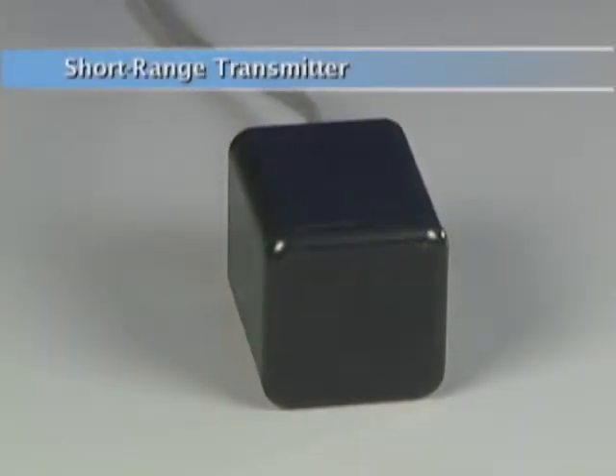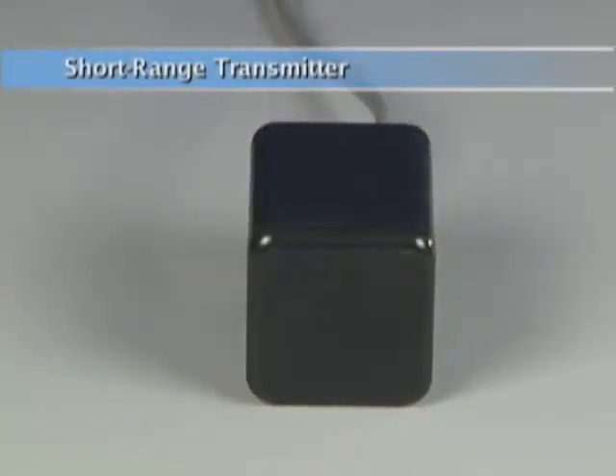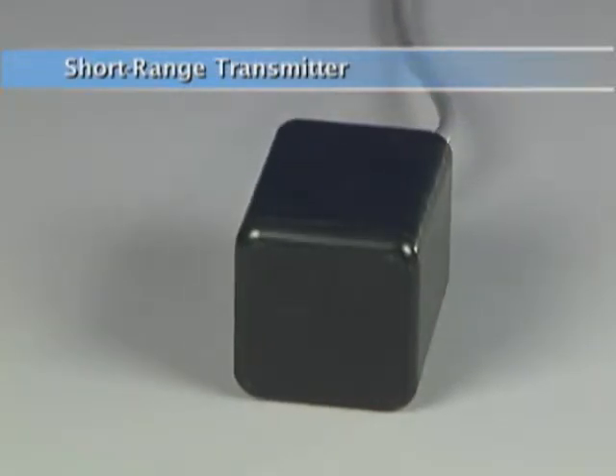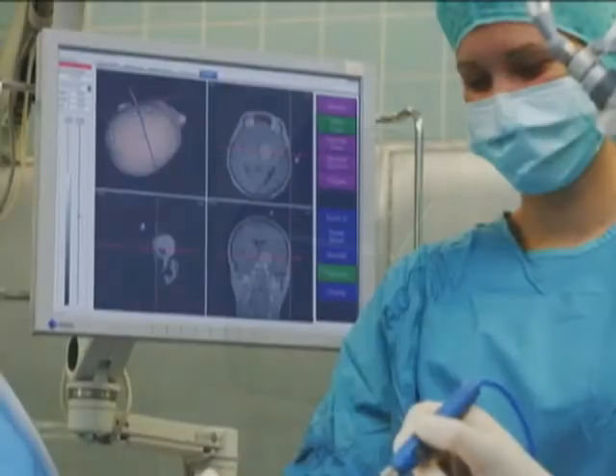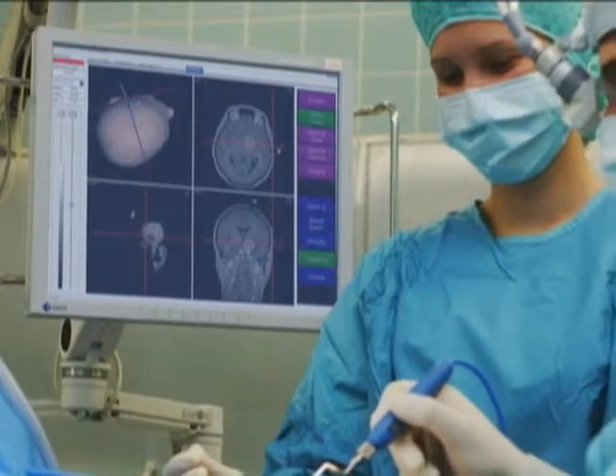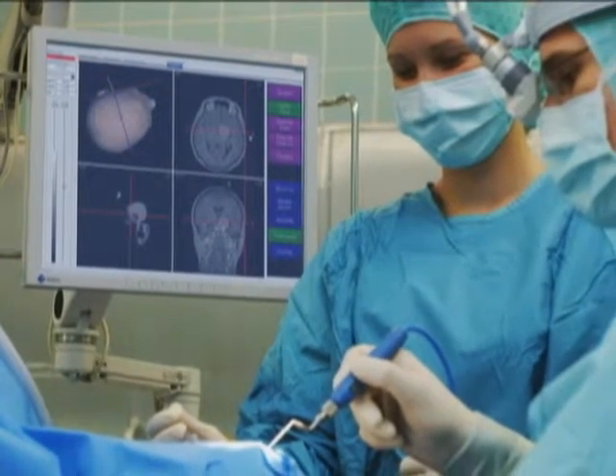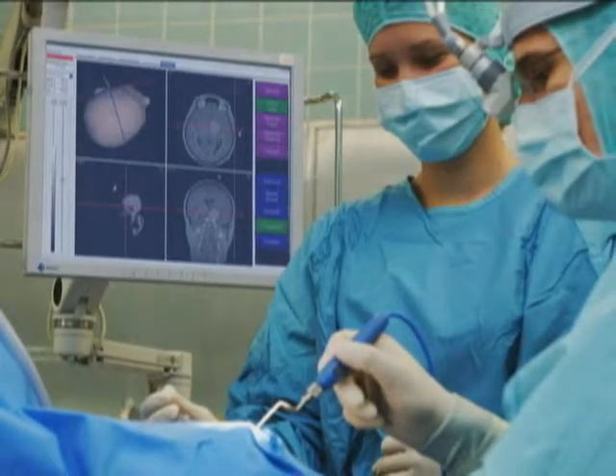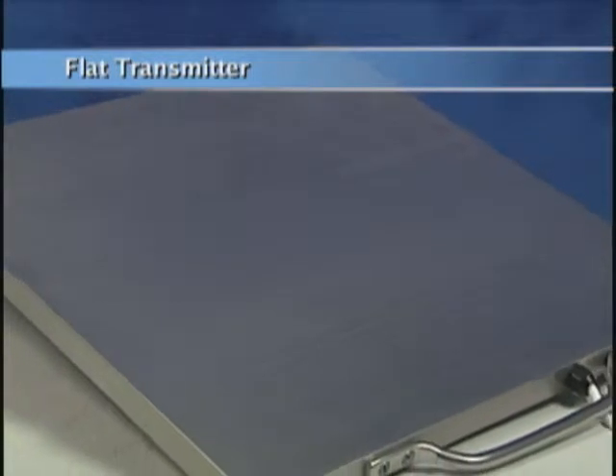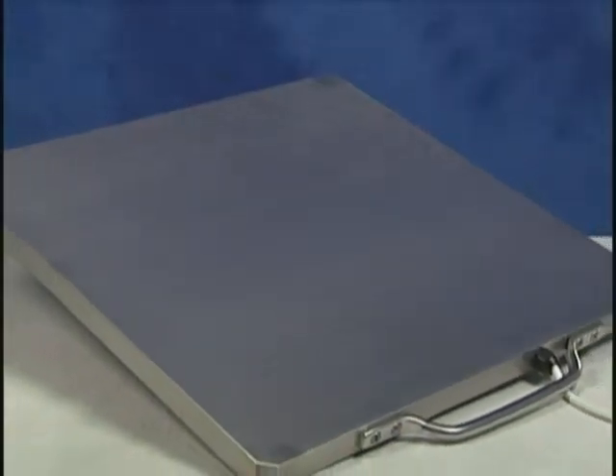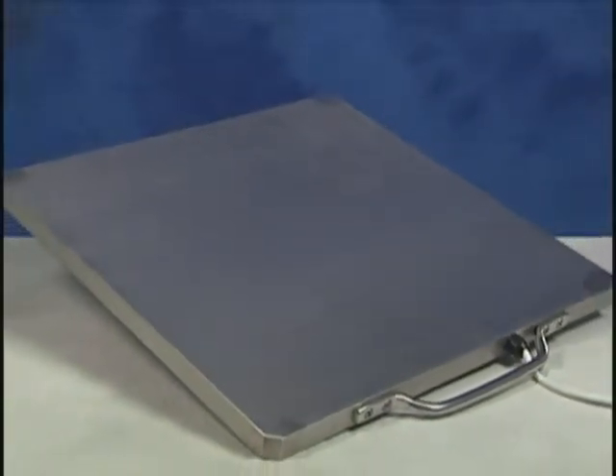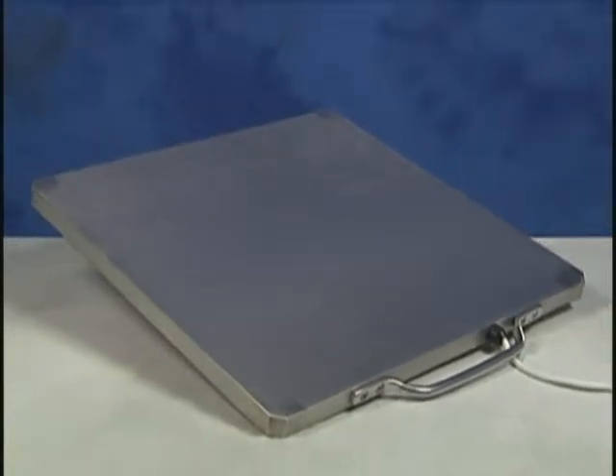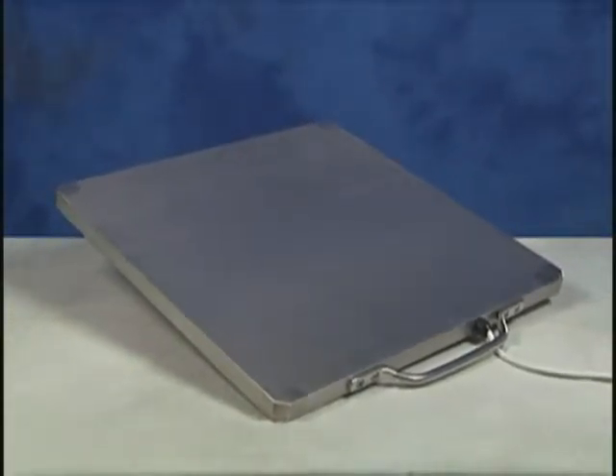The short-range transmitter is a lightweight field generator that can be brought very close to the patient. Small and unobtrusive, it can be draped while in the sterile field and still deliver clear field signals to its sensors. And the flat transmitter: this breakthrough design overcomes ferrous metals often found in common medical procedure tables. Its built-in shield blocks all interfering metals below its surface while accurately tracking sensors inside or above the human body.